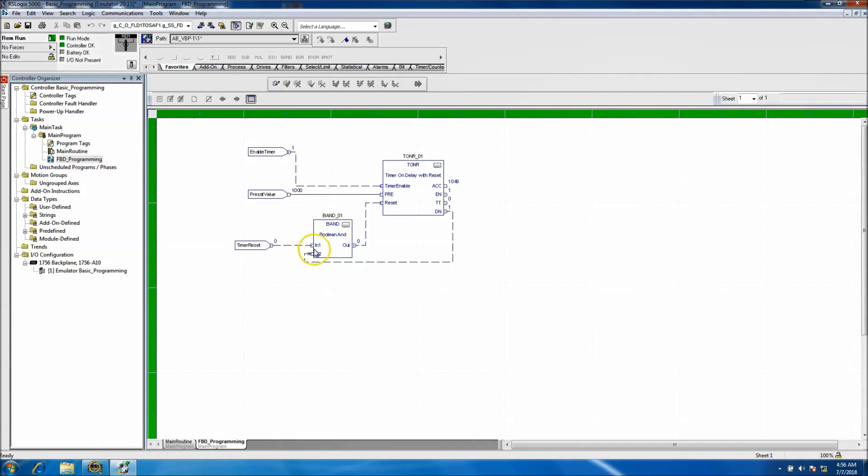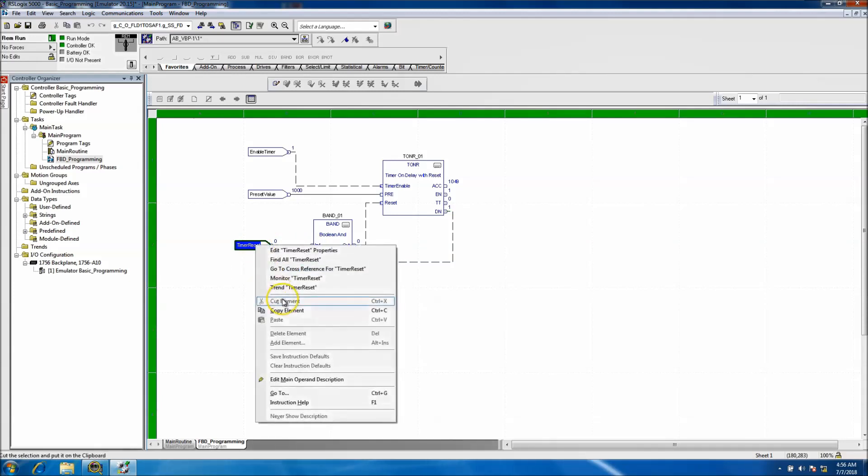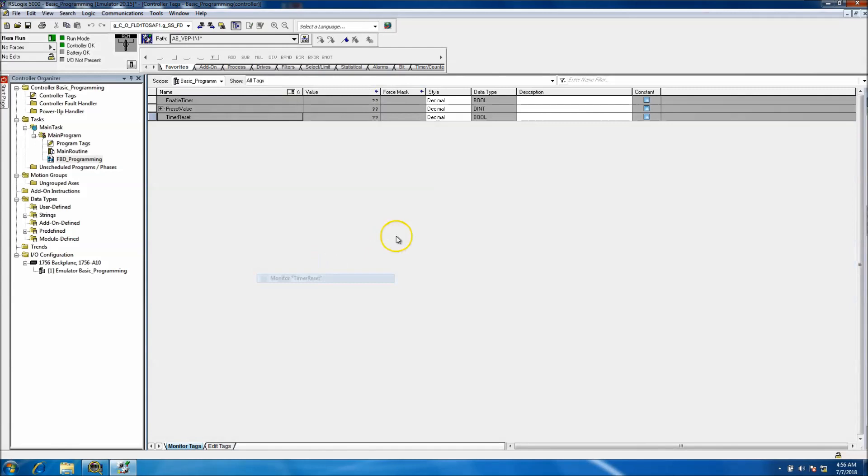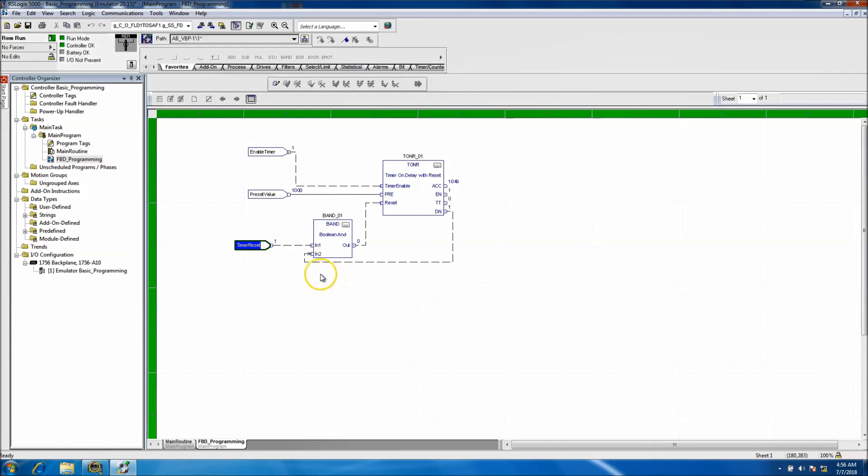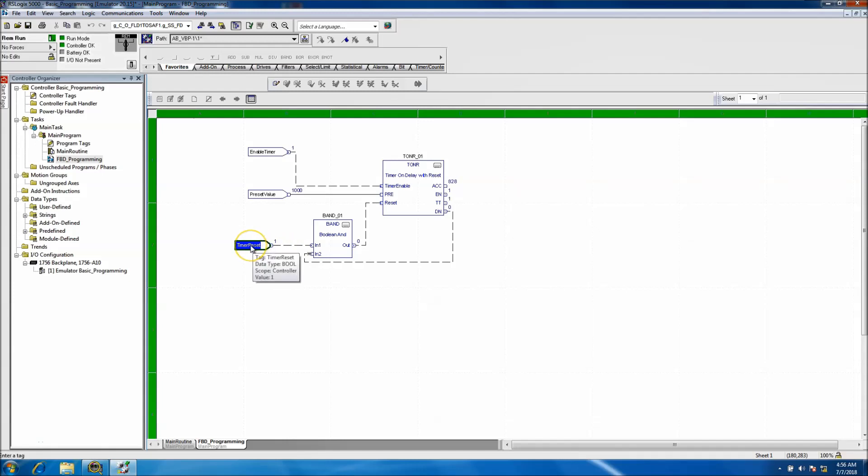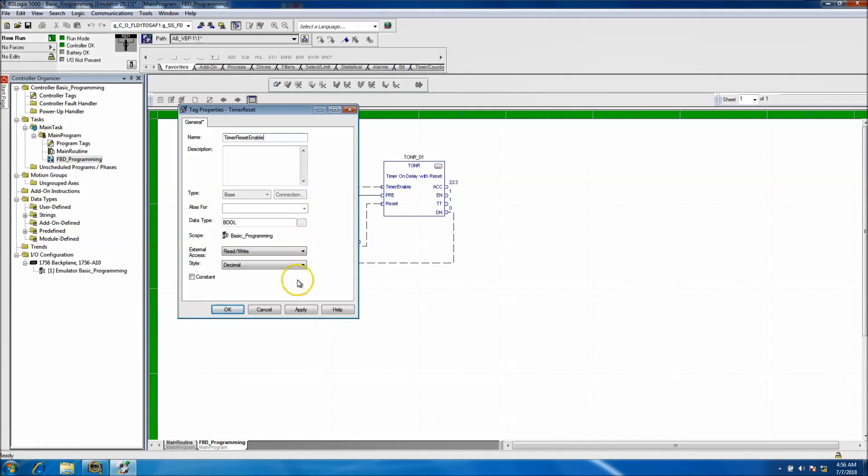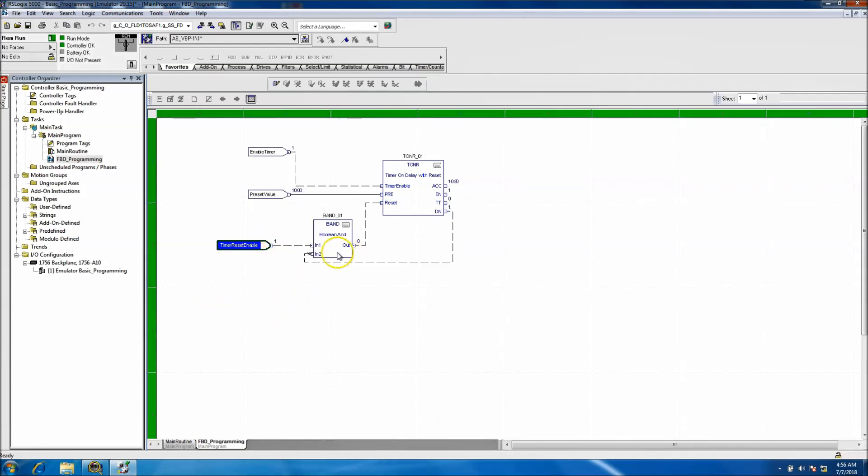So in this case we're not resetting right now. So let's go back here and let's turn that into a one. So now we're having the reset only work off the done bit if the reset timer is on. So you can almost call this a reset timer reset enable, for that matter, because that's really what it's doing. It's allowing the reset to happen.